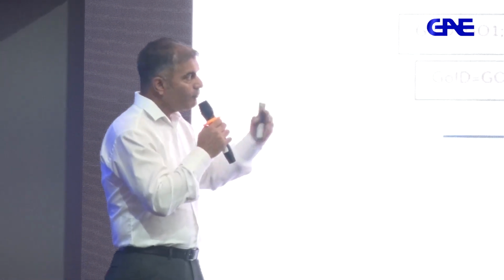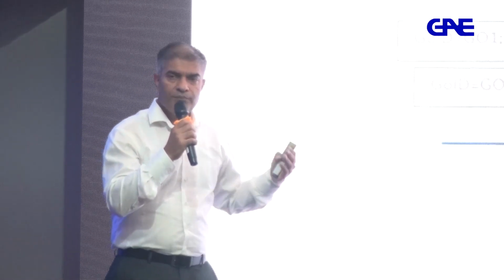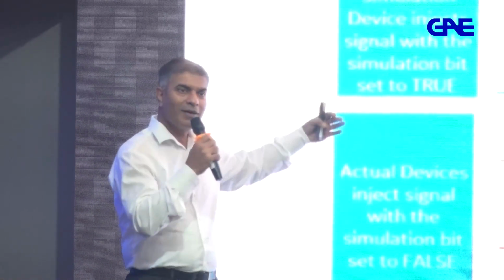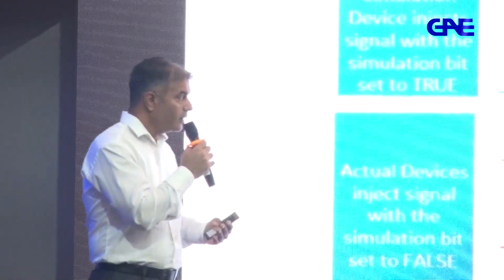Basically in 61850 edition 2, there are two very important things. One is a test mode and one is a simulation mode. So with combination of test and simulation, basically what we can do is when the substation is running, when your secondary equipment is protecting the feeder, you can still test the function within the relay without taking shutdown, without isolating anything, just by changing the test mode. Because I don't have enough time, I can't go through all the slides in detail.